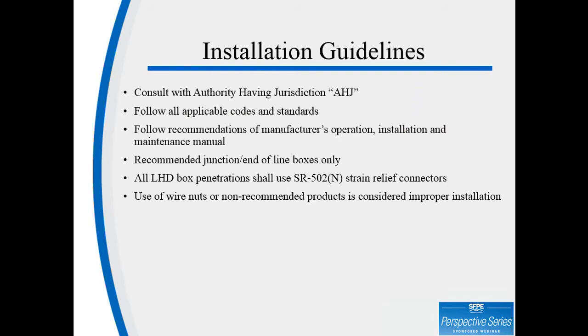Installation guidelines for LHD. Consult with the authority having jurisdiction, better known as the AHJ. Follow all applicable codes and standards. Follow recommendations of the manufacturer's operation, installation, and maintenance manual. Use recommended junction and end line boxes only. All LHD box penetrations shall use SR 502 strain relief connectors. Use of wire nuts or non-recommended products is considered improper installation.